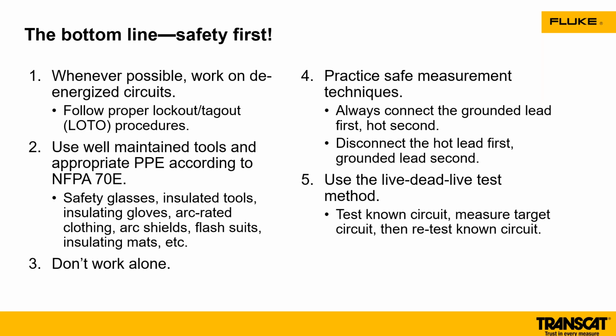That's a key win on that. And just practice those safety measurements. This is a great technique when you're doing voltage measurements. You always want to connect your common, or your black one, to a ground, and then you will check with your hot, do your measurement, pull off your hot, and then pull off your ground. It's just a great safety measurement.